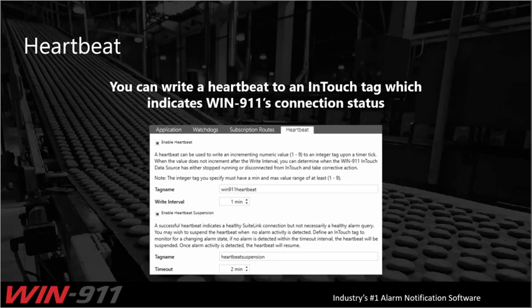The heartbeat writes an incrementing value from 0 to 9 on an integer tag. Once the heartbeat reaches 9, it rolls back to 0 and keeps repeating that forever. If the tag fails to update — it doesn't get that write value to update — you can assume that WIN911 has probably lost the connection into InTouch and is no longer able to send updates or even receive alarm information. It can raise that flag for you.